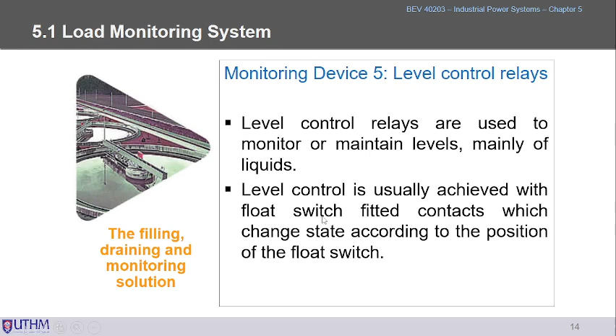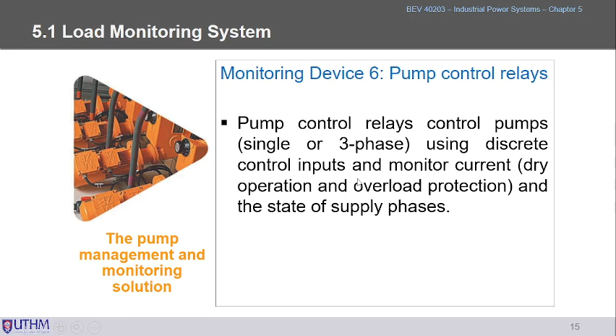For pump management, of course we can use pump control relays. They can control either a single-phase or three-phase pump. We can monitor the digital control inputs and the currents, that is, dry operation and overload protection for the pump.